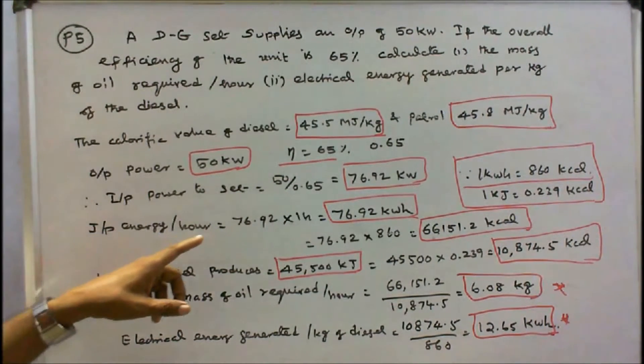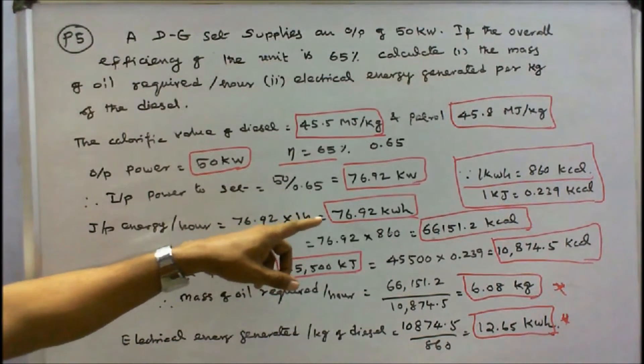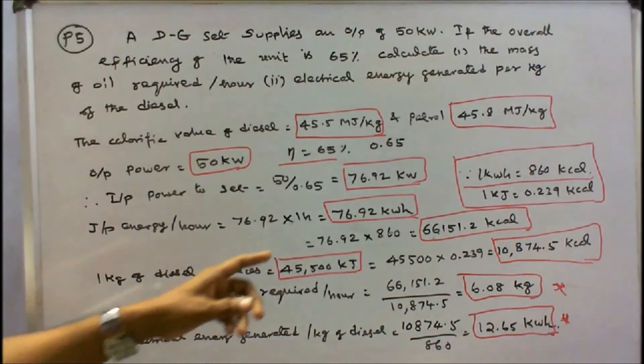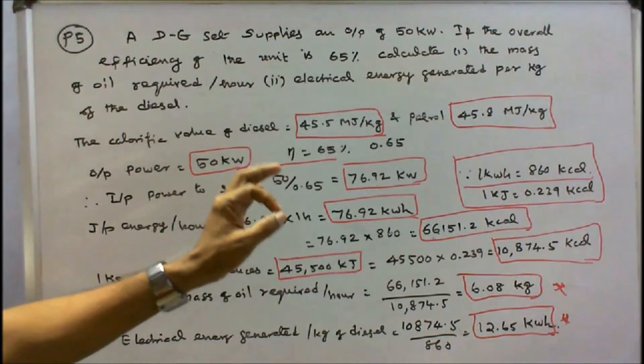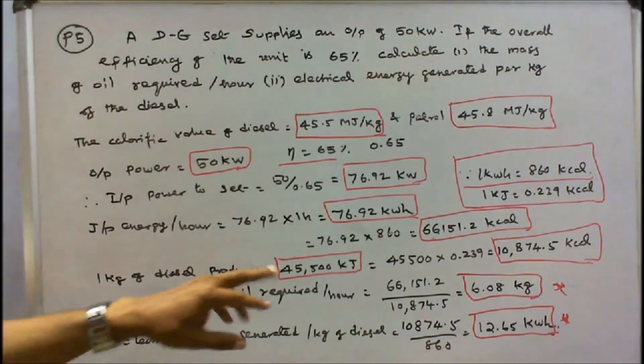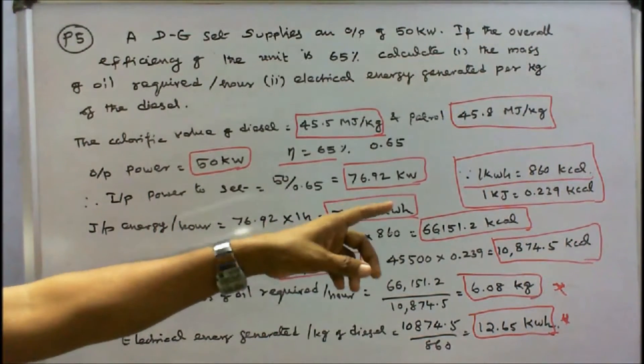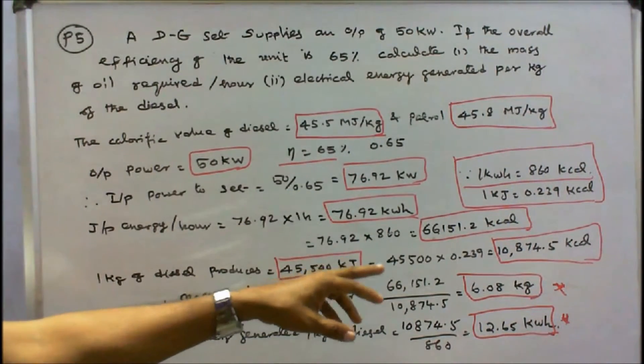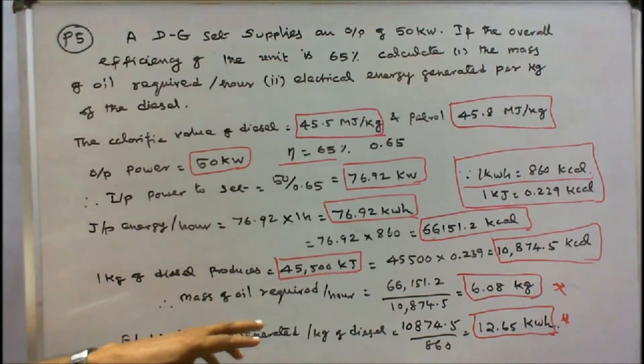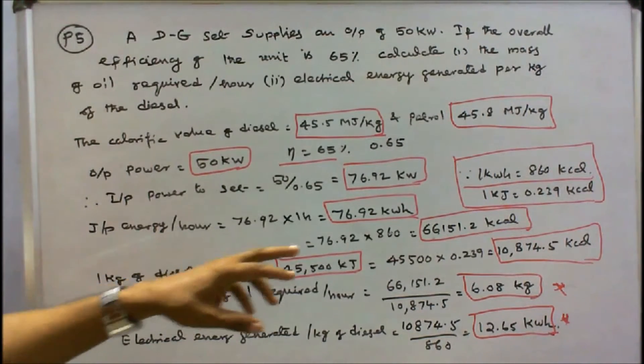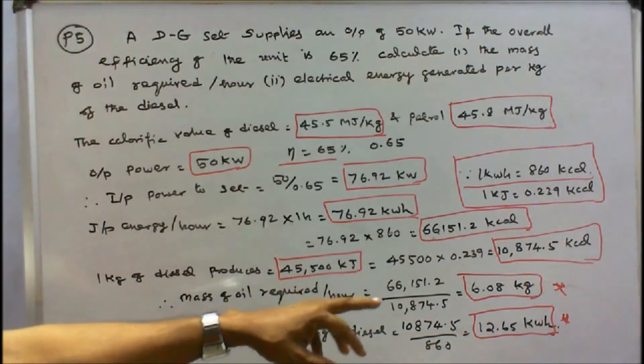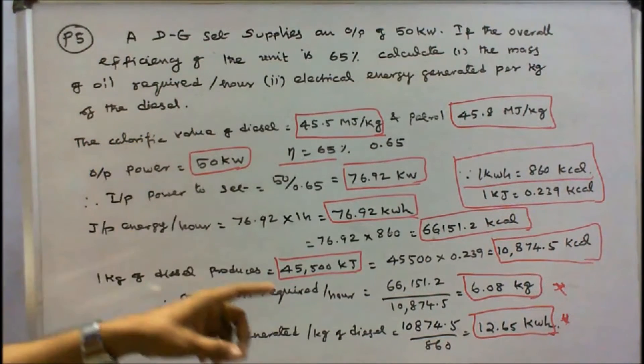Input energy per hour is 76.92 kWh. Converting to kilocalories using 1 kWh equals 860 kcal: 76.92 into 860 equals 66,151.2 kcal. One kg of diesel produces 45,500 kJ. Since 1 kJ equals 0.239 kcal, that is 45,500 into 0.239 equals 10,874.5 kcal per kg. Therefore mass of oil required per hour is 66,151.2 divided by 10,874.5, equal to 6.08 kg per hour.